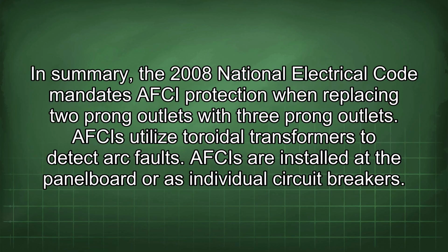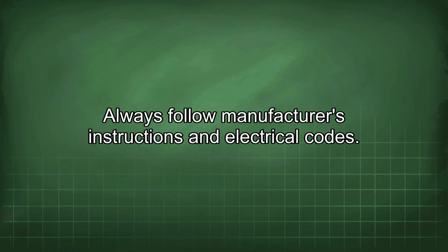In summary, the 2008 National Electrical Code mandates AFCI protection when replacing two-prong outlets with three-prong outlets. AFCIs utilize toroidal transformers to detect arc faults. AFCIs are installed at the panel board or as individual circuit breakers. Always follow manufacturer's instructions and electrical codes.